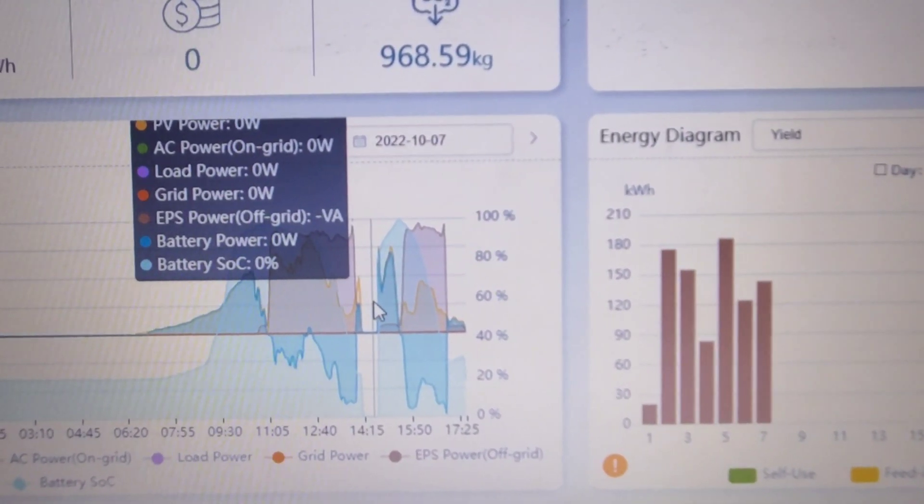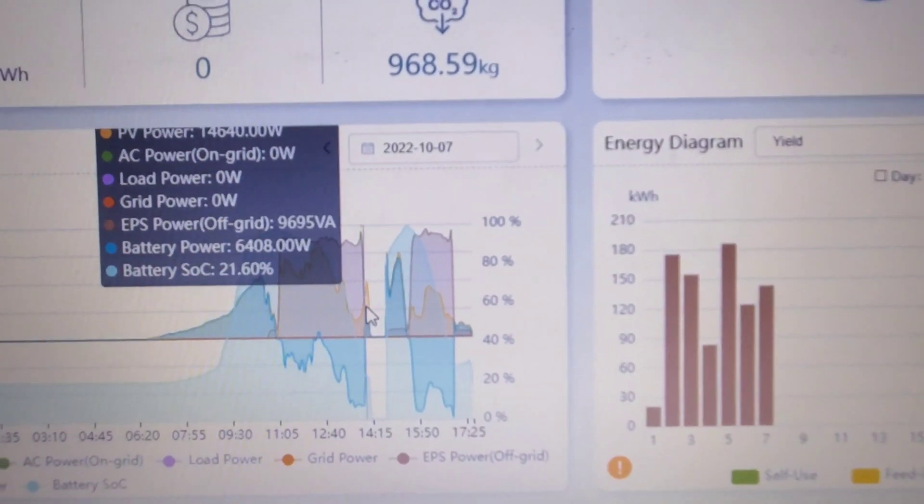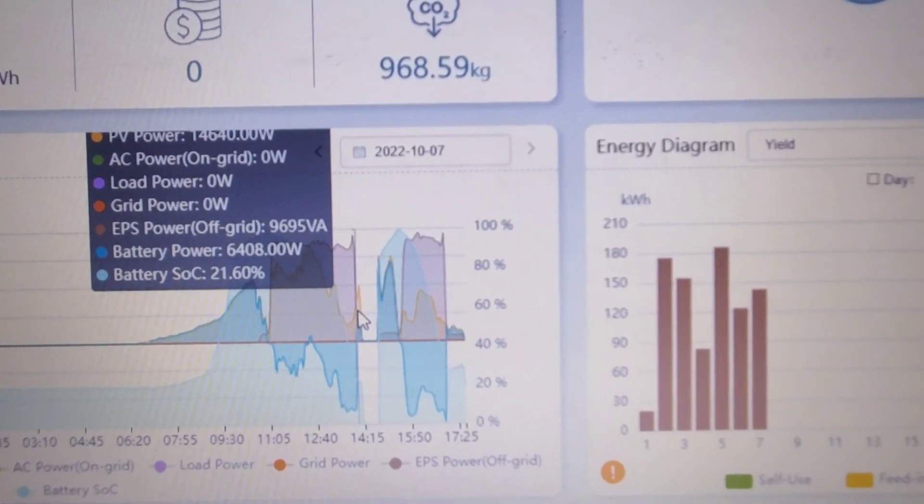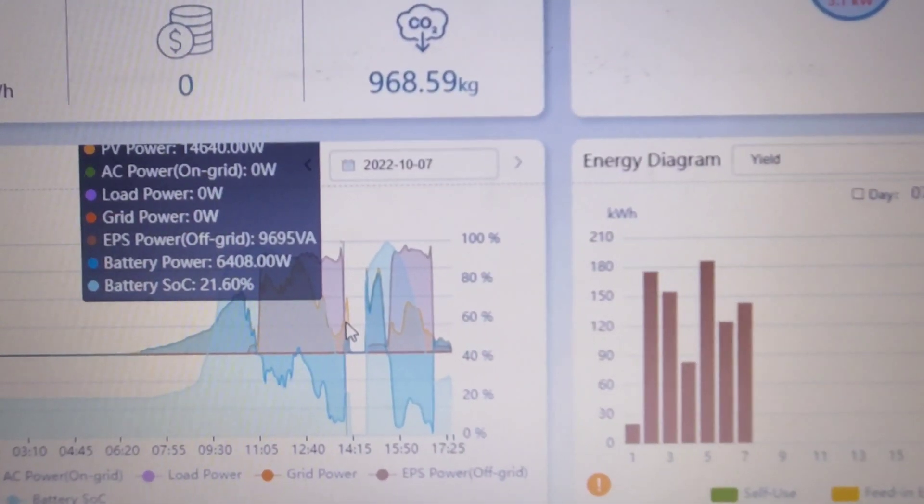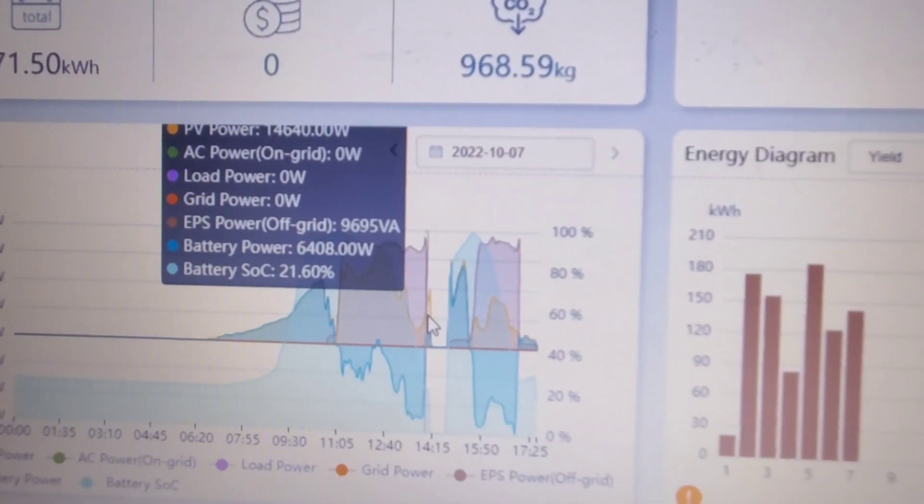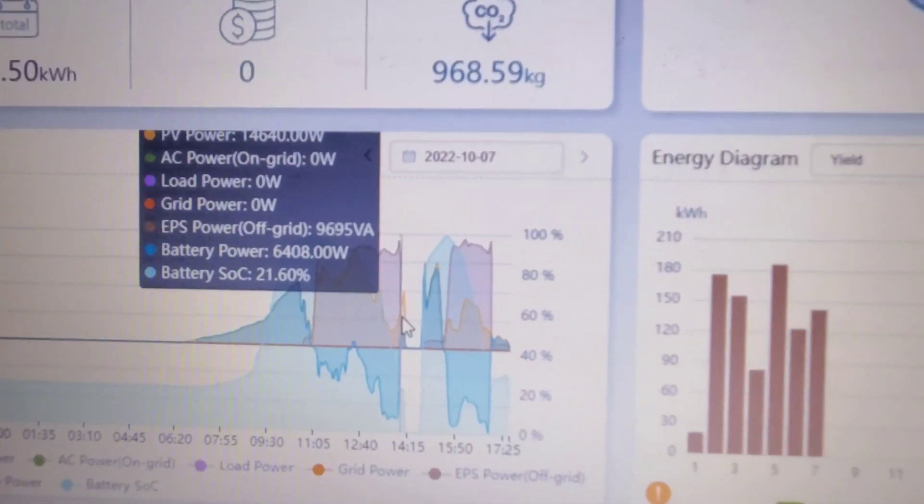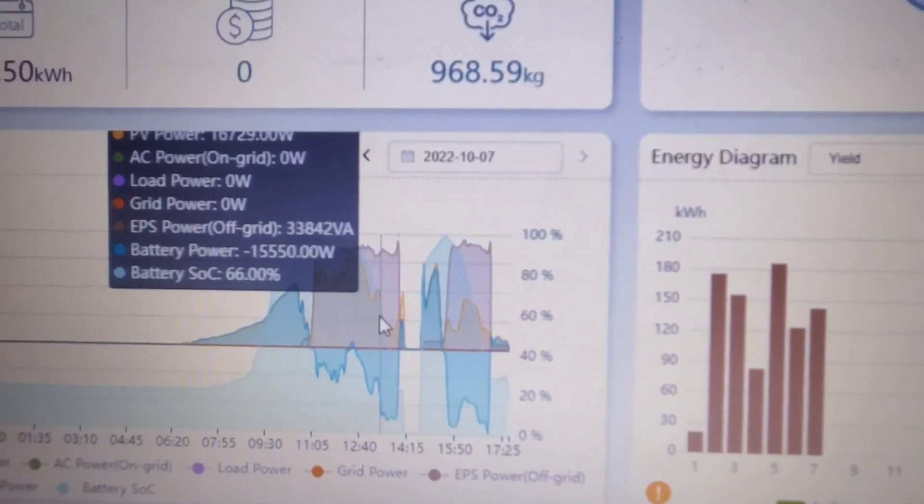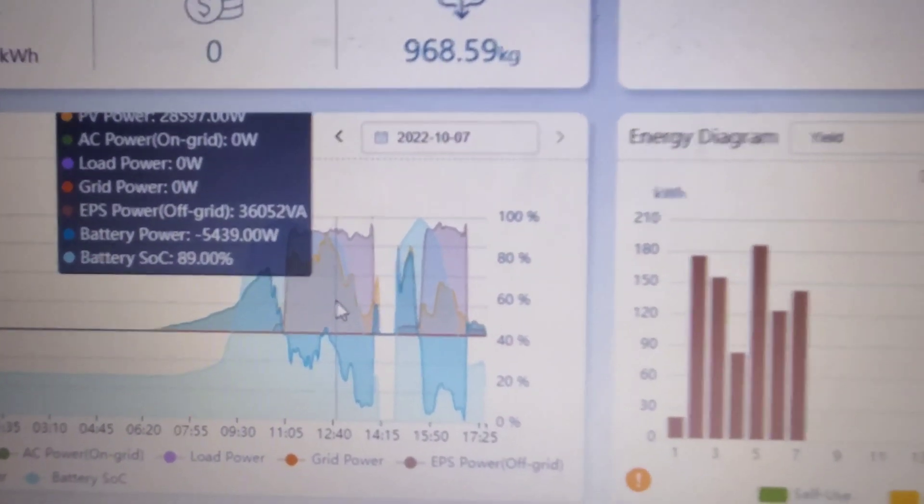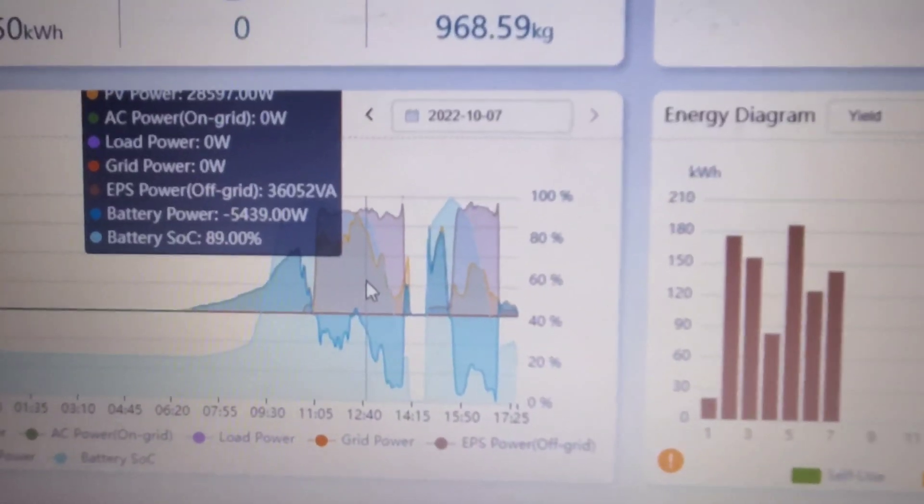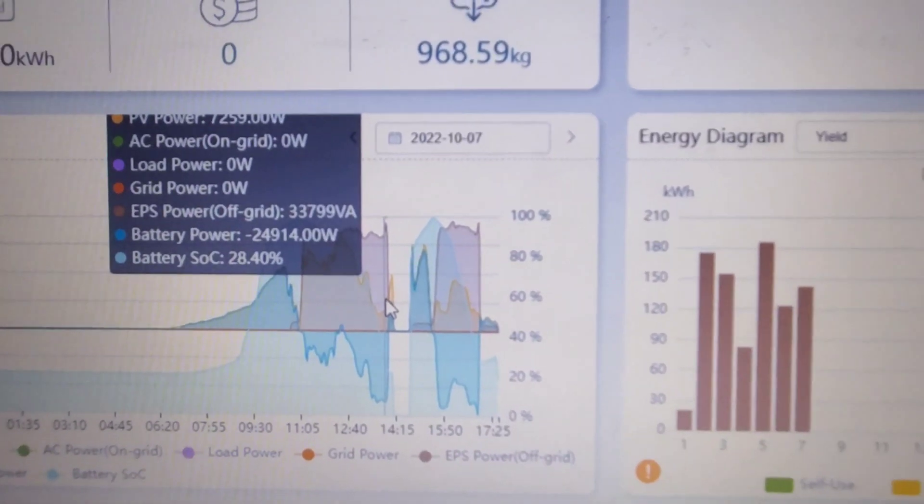Here we shut it off. Actually, we didn't shut it off—what happened is the inverter started to drop. Since we have different batteries on different inverters, it started dropping the first inverter, then the second inverter because we hit a low battery cutoff, then drop the third inverter.